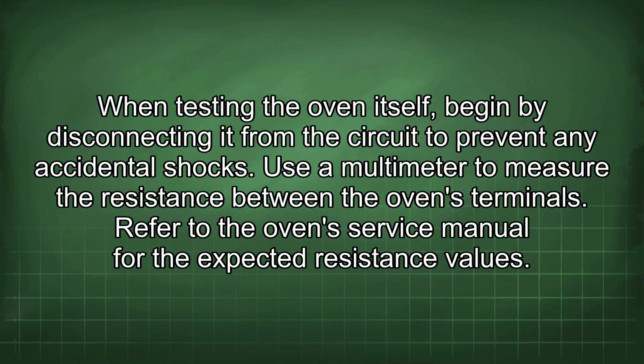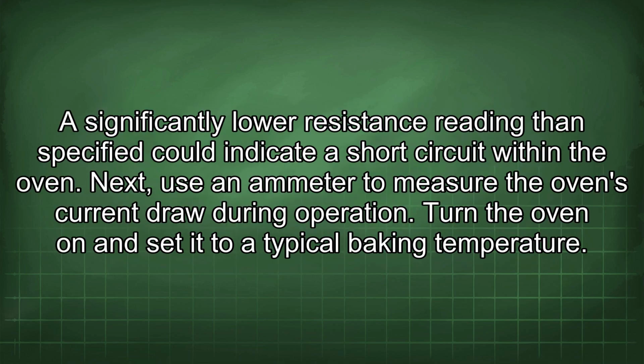When testing the oven itself, begin by disconnecting it from the circuit to prevent any accidental shocks. Use a multimeter to measure the resistance between the oven's terminals. Refer to the oven service manual for the expected resistance values. A significantly lower resistance reading than specified could indicate a short circuit within the oven.